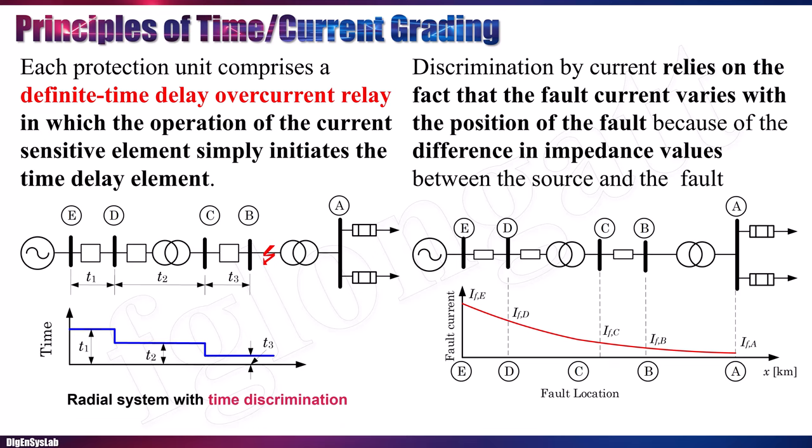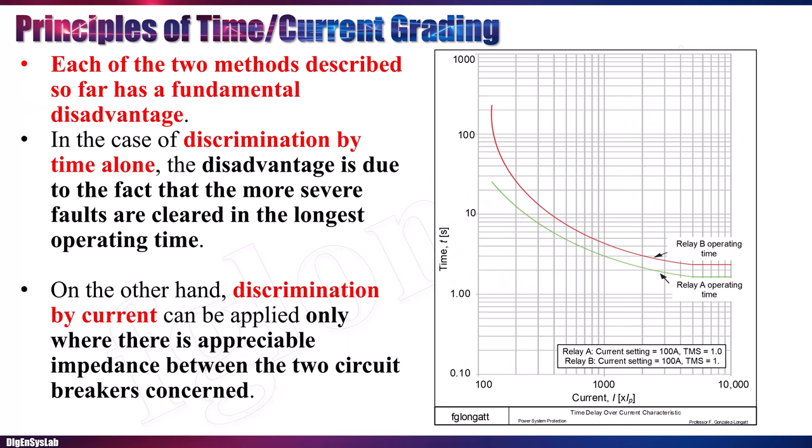The other way is to use short circuit currents. The farther you are from the generation point, the lower the current. The short circuit level at busbar A is very low compared to the short circuit level near generation at point E. We can use the magnitude of the short circuit current to create discrimination. However, in some configurations this becomes difficult because the electrical distances or magnitudes become very small. For that reason, in modern distribution systems we use a combination of time and current grading.